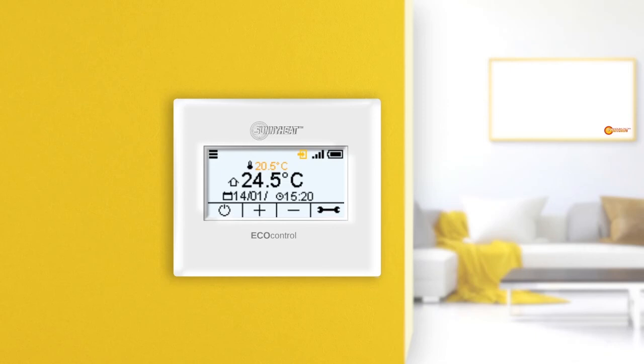If the motion sensor is activated and there is someone in the room, the presence symbol appears on the main display. If there is no one in the room and the delay time has expired, the absence symbol appears on the main display. The set point temperature changes to the set point temperature of the motion sensor. If someone is in the room again, the symbol changes back to the presence symbol and the set point temperature changes back to the normal set point temperature.